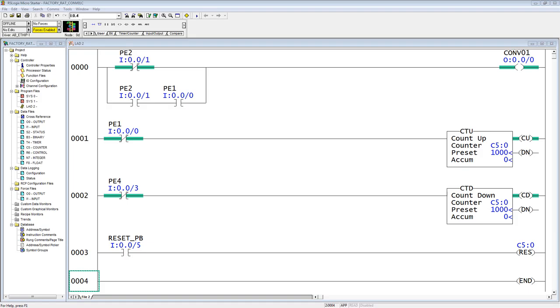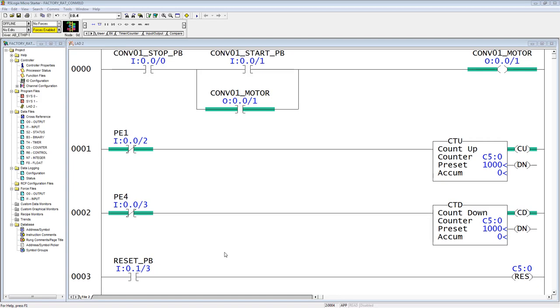We're going to eliminate the first rung and we're going to change the code that actually controls the conveyor motor, but we're going to keep our counters. Two quick things to point out: I moved the conveyor motor to output 1. I want to leave output 0 open for a fault light. I also took input 0 and 1 away from the photo-eyes, and I moved photo-eye 1 to input 2.